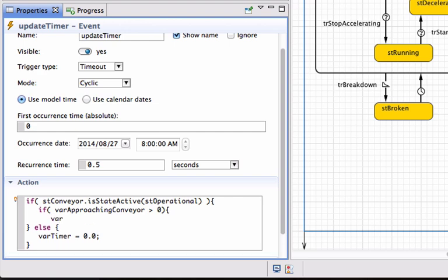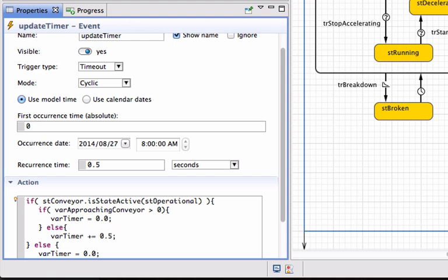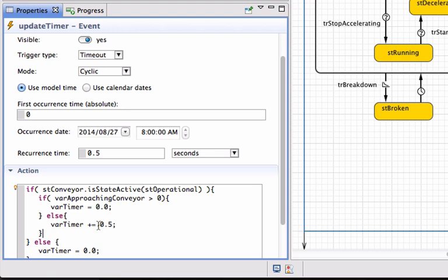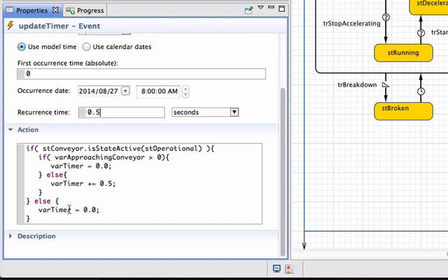If somebody is approaching, reset the timer to zero because the machine cannot even consider decelerating. Otherwise, increment the timer variable by half a second. I do the 0.5 addition because I am checking this timer every half a second — if the recurrence time were one second, I should add one second accordingly. To recap: check if the conveyor is in operational state; if so, check if anybody is approaching — if yes reset timer to zero, if no increment by 0.5 seconds; if not operational, reset timer to zero.